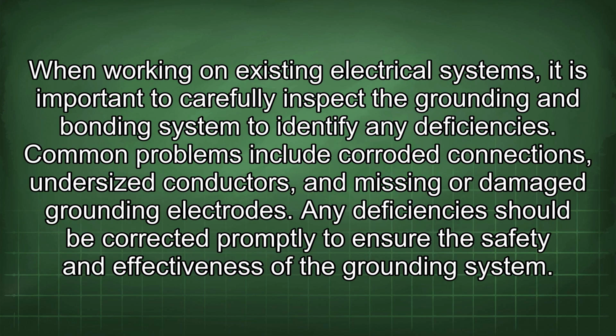When working on existing electrical systems, it is important to carefully inspect the grounding and bonding system to identify any deficiencies. Common problems include corroded connections, undersized conductors, and missing or damaged grounding electrodes. Any deficiencies should be corrected promptly to ensure the safety and effectiveness of the grounding system.